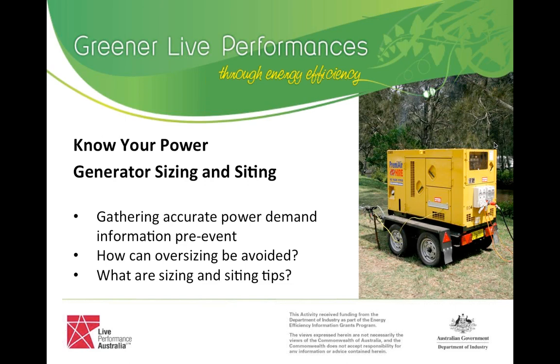Obviously if you go to a smaller generator, you're saving the daily hire rate as well, so there's a cost saving involved. We can measure the difference in fuel consumption rate between, say, a 100 KVA and a 150 KVA generator, and over a four-day event that could be significant. It's like hiring a car — you're hiring a V8 versus a 1.3-litre. At the outset you're going to have a higher fuel consumption for a larger generator. The risk is if you're not using the capacity, that's when you become inefficient.